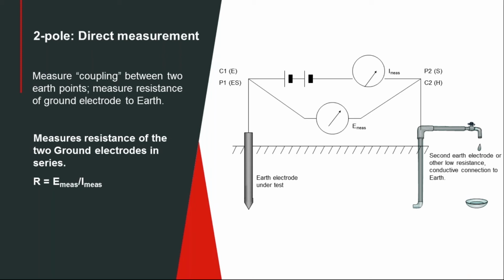And that the return path through the water pipe system, where you may have used a long metal fence post, for instance, sometimes you could use that. But you've got to hope that that's contributing very little to your measurement. So your number is going to be a little bit high, but not too bad. Now, this is basically what you would call a cheap and dirty type of test. Why would you want to do it at all? Well, a couple of things. First of all, it is cited in IEEE 81, which is the ground testing standard. So if you want to cite an authority, if you want to tell a client, this is the best I could do, and it might be okay.